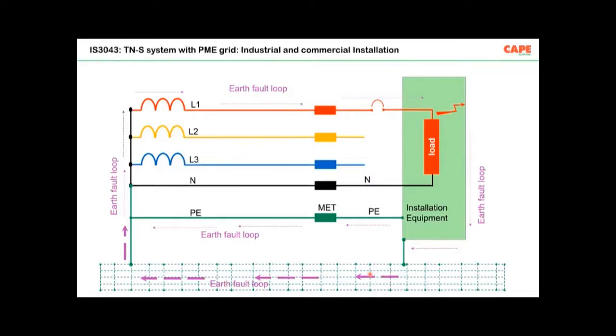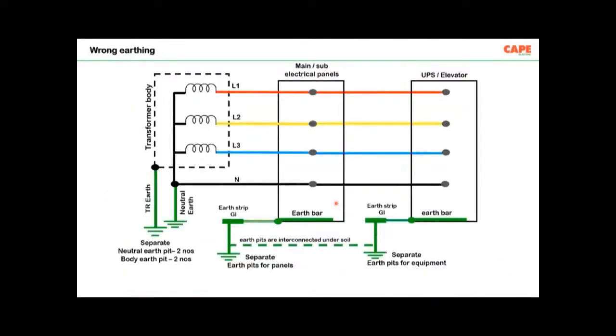This kind of connection and earthing is mandatory, not only for fault loop impedance reduction, but also, for example, to reduce the voltage of induced effects such as from lightning. It is necessary to reduce the shock voltage during a high voltage fault. So all these things are very well documented, but basically this is how you are supposed to make earthing in your building, if it is an industrial or commercial building.